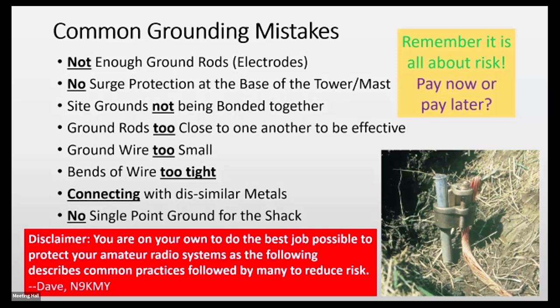The technician who took me to the roof said every time they get lightning up there, his elevator goes out. There was a ground rod, a big ground electrode, going up on that building — they called it the Honors Building. Every time they got a lightning hit, it was mounted on the side of the elevator equipment room. I said, open the door of the room. He opened it, and I looked inside — there was the elevator control panel on the other side of the wall.